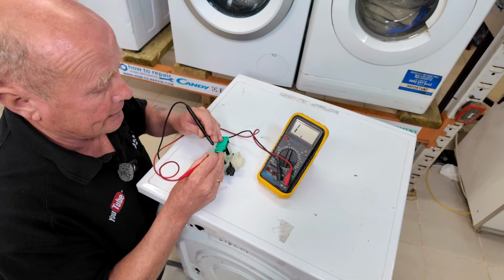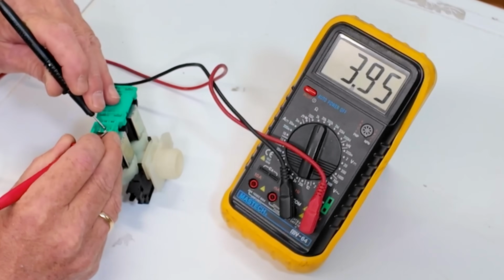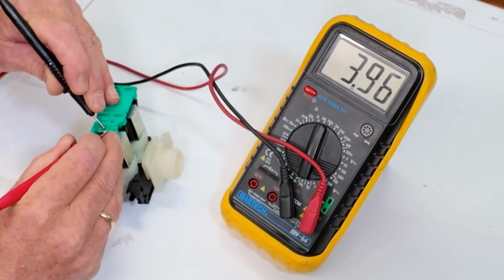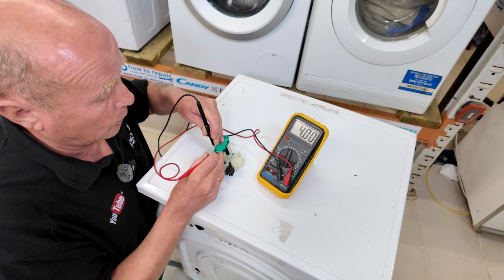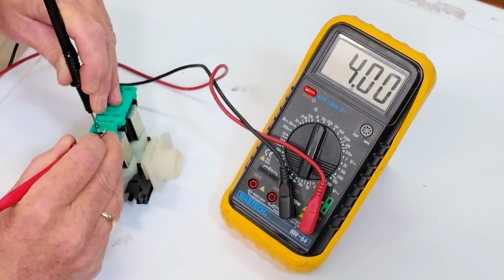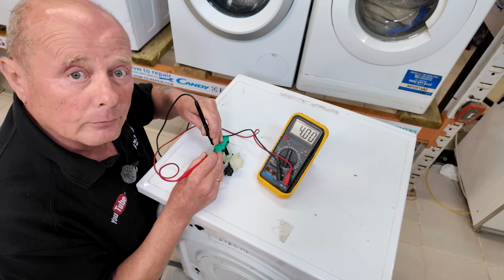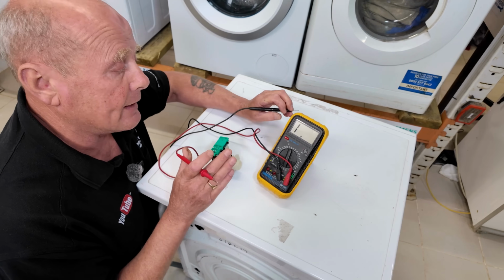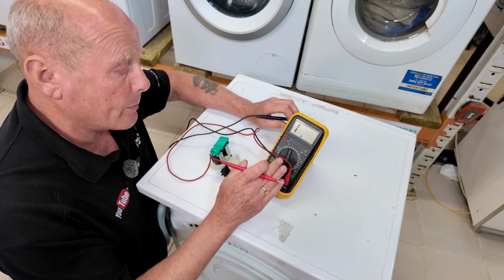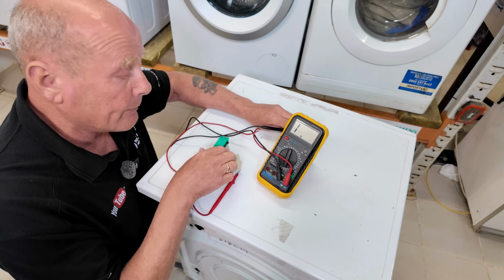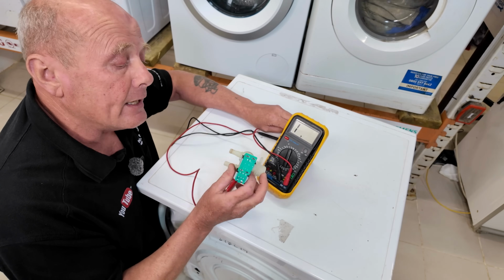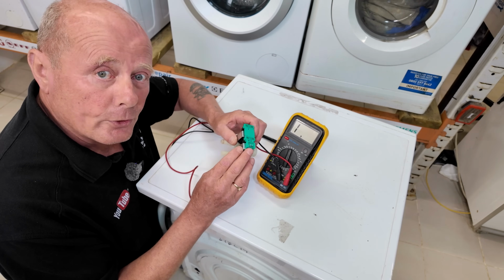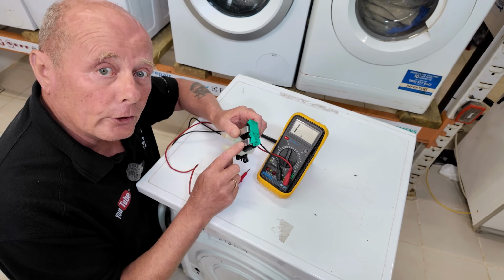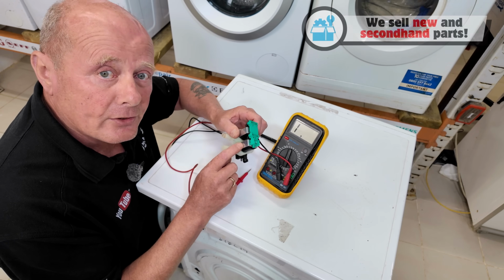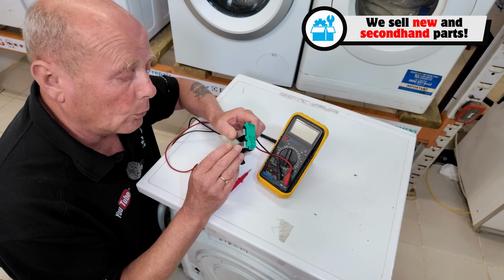So if we look here, connecting on pin 1 to pin 2, we have a reading of 396. And if we go pin 1 to pin 3, we have a reading of 400, which is close enough. That is a very accurate reading, and you must remember my meter is not calibrated. This is a good water valve. If either of those circuits were open circuit, then you have a coil that has failed and will need replacing, or you will need to replace the whole water valve.